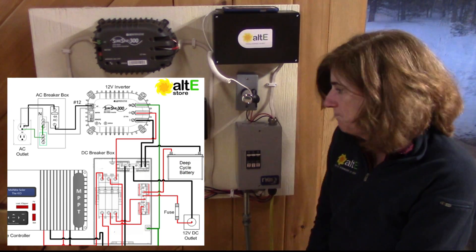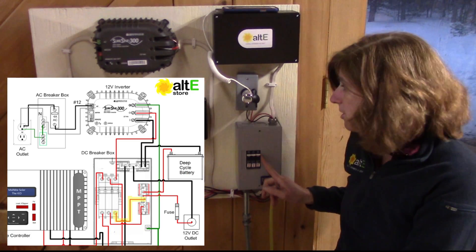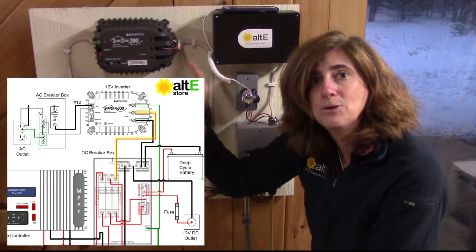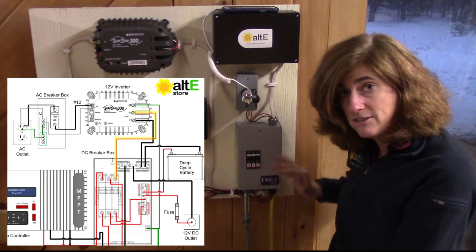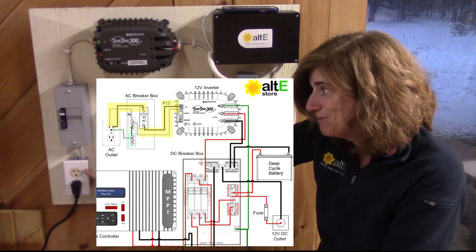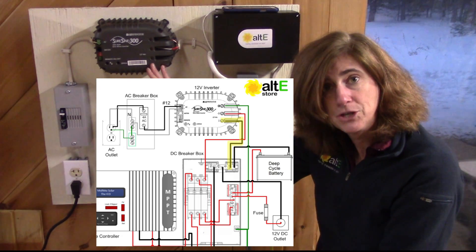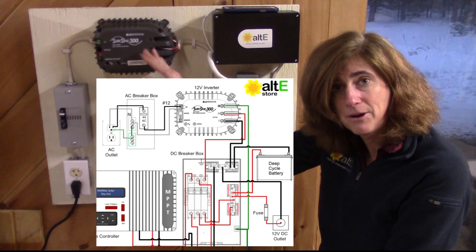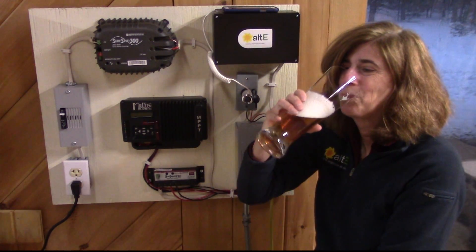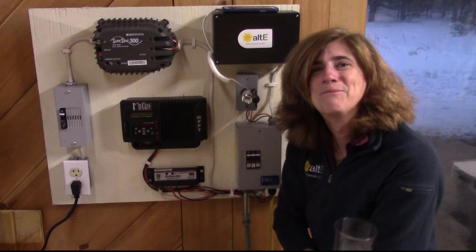From the positive bus bar I'm going through a breaker up to my inverter, which takes 12-volt DC from the battery and converts it to 120 volts AC. The positive goes from the positive bus bar to the inverter positive-in, then out to an AC breaker box, to the outlet, to the kegerator. The negative bus bar connected to the battery negative goes straight up to the inverter as well. That gives me my nice cold beer — cheers! Make sure to check out our website altestore.com, where we've been making renewable doable since 1999.